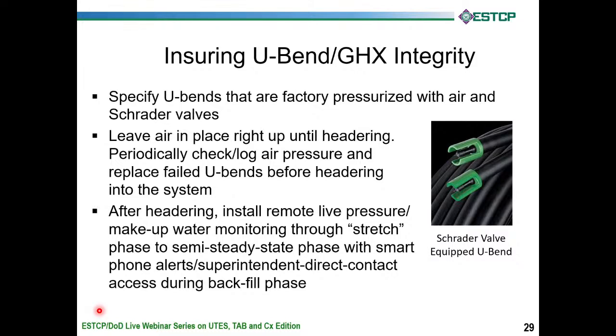And as Brandon showed in the other slides, we like to install live pressure monitoring. And it is a little tricky with HDPE, as Brandon alluded to. We observed at the BTES system at the Marine Corps base in Albany, that was the source of some of these slides here, that as the sun heats the pipe up during the day, the pipe grows faster than the water grows, and so the pressure drops. It cools down at night and the piping contracts, and you start to see these diurnal cycles that are not indicative of a leak.